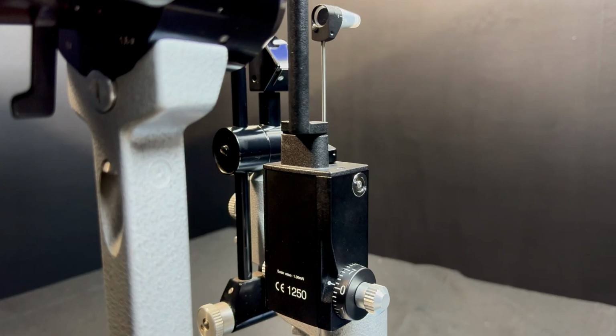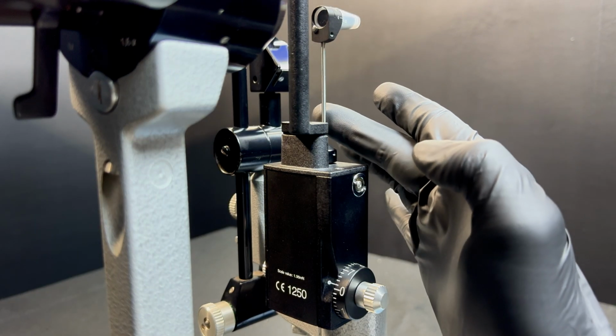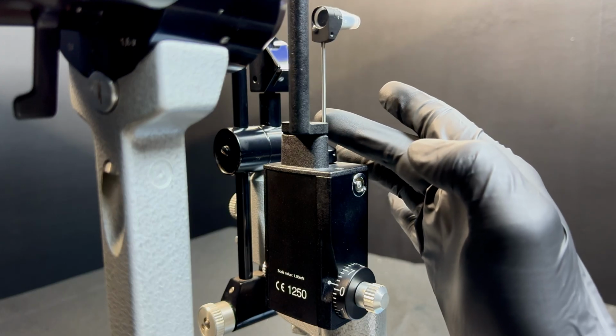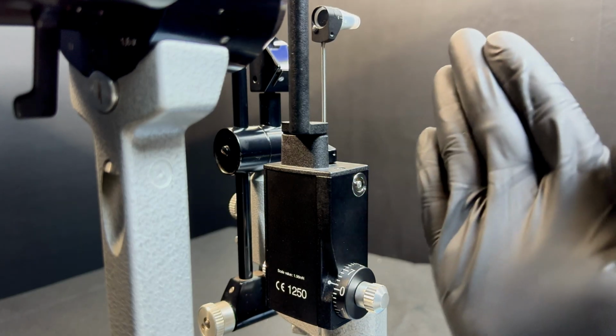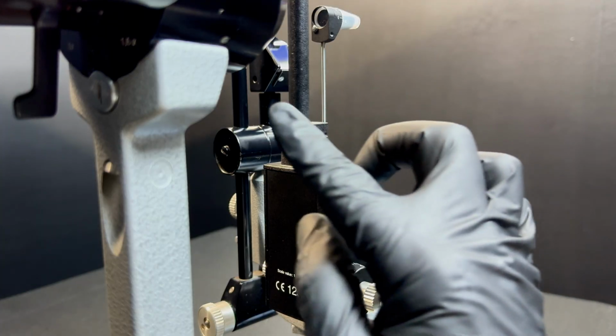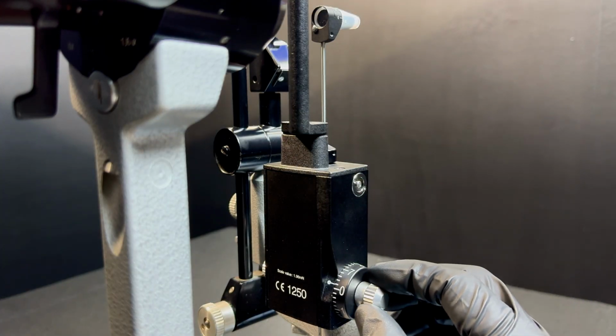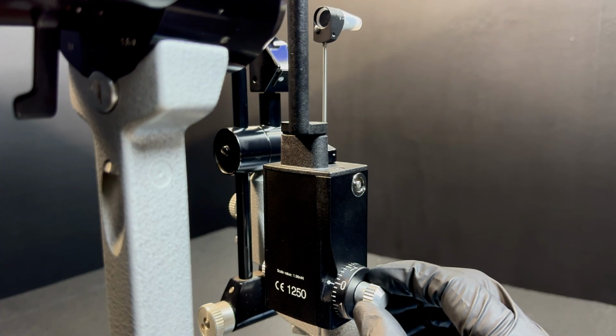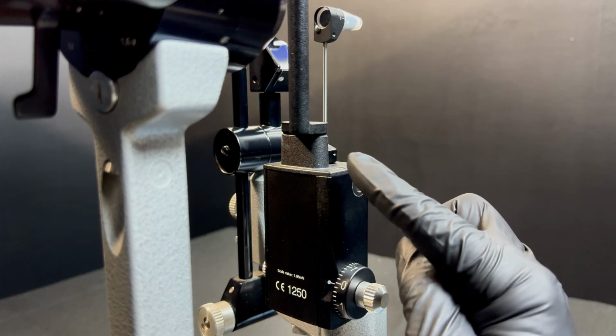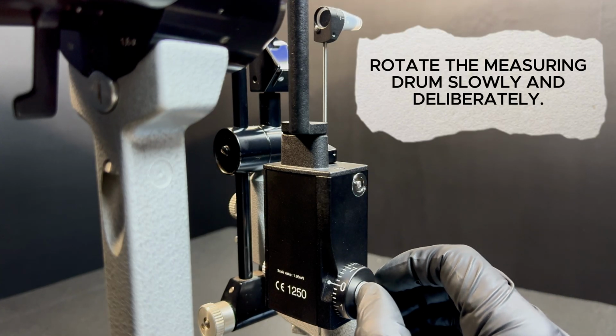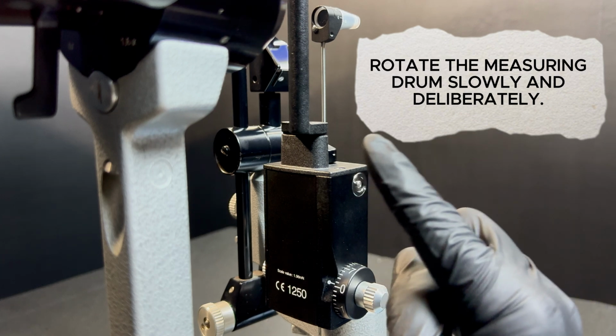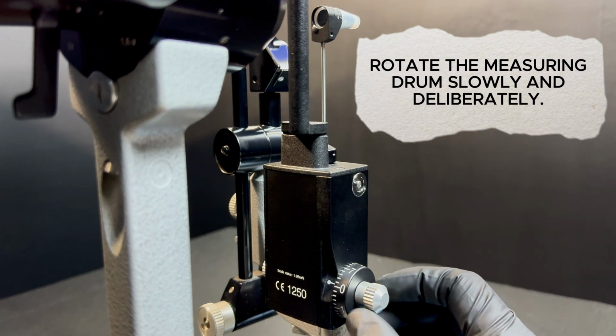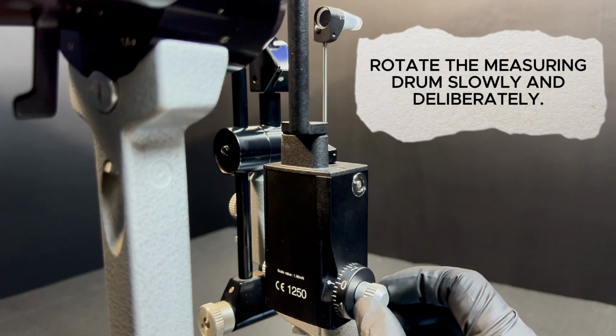Place the tonometer in its normal operating position in front of the slit lamp optics. This is the feeler arm. It responds to movement of the measuring drum. In this position, just above 0, it is resting toward the operator side. As the measuring drum is rotated further, the feeler arm falls forward. When the drum is rotated back, the feeler arm falls back. The tonometer passes calibration at 0 when the feeler arm falls forward and backward, as the index mark moves just past and just before 0. This confirms the feeler arm is balanced.